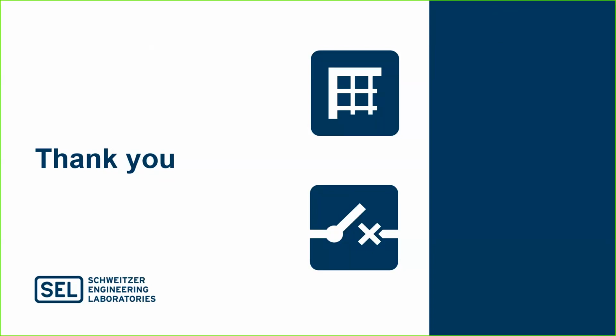Good. Thanks, Brian. Another question is, how does FLISR behave in relation to COM failures? So if a communications failure occurs, how does the FLISR scheme automatically attempt to isolate or restore, for example? Right. Okay. So the safest thing you can do in the event of a COM failure is to disarm FLISR on that feeder until that COM failure resolves.